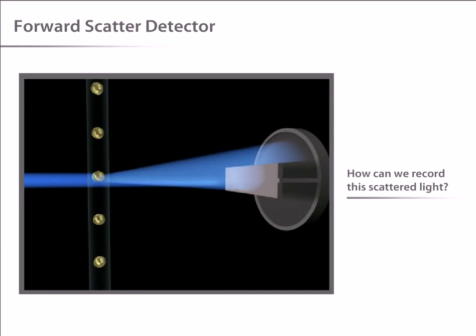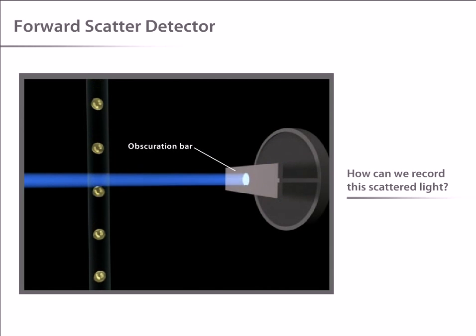Light is quantified by a detector that converts its intensity into voltage. In most cytometers, a blocking bar, called an obscuration bar, is placed in front of the forward scatter detector.